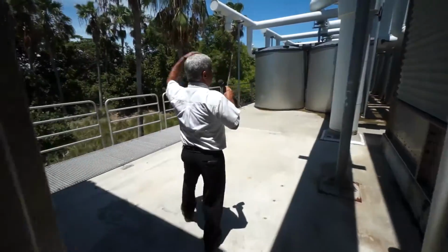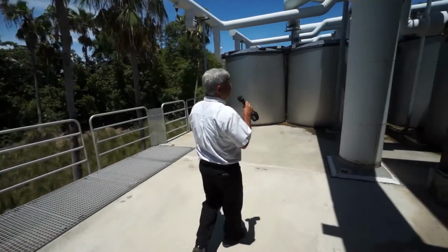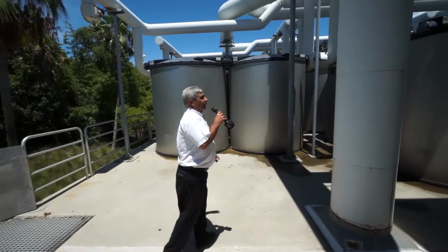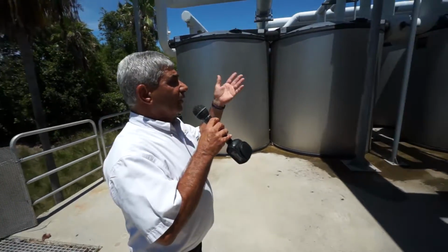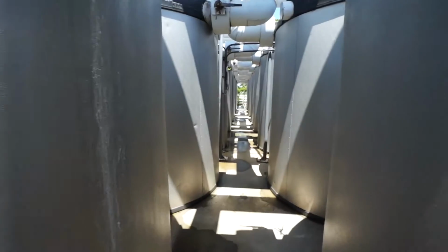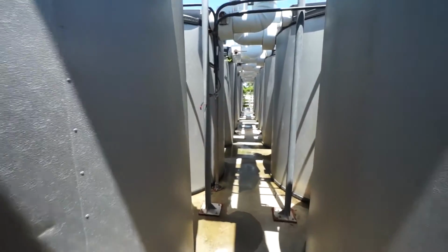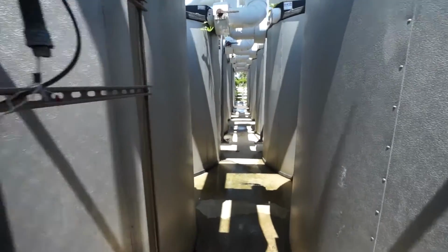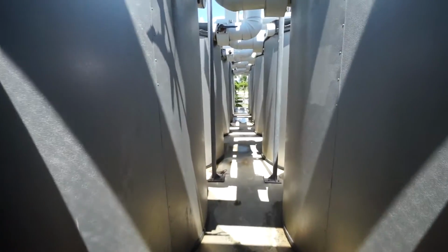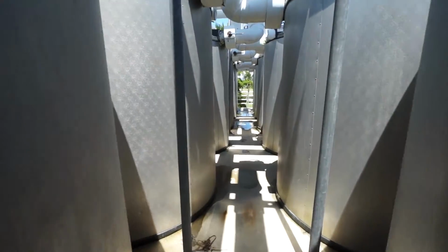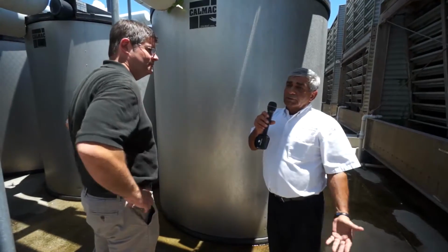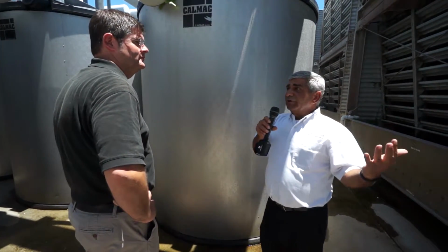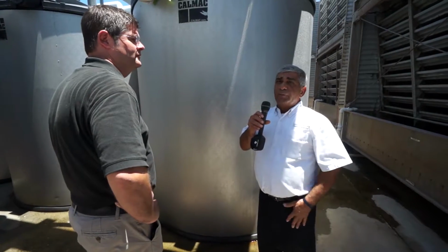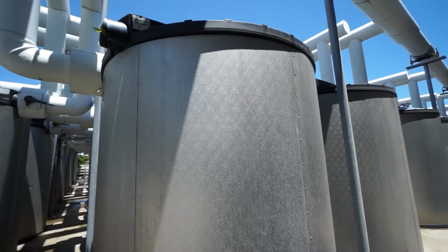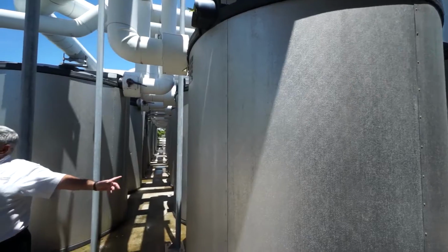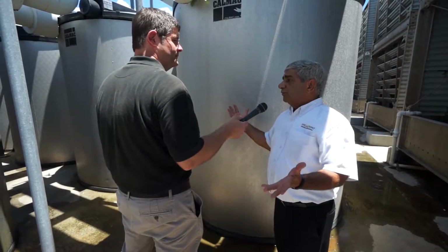Okay, now we're coming up on our ice tanks, which we call our ice farm. There are 240 of these tanks, 120 upstairs and 120 downstairs. It's just a solid chunk of ice in there with a coil running down with glycol through it, and through thermal expansion, I'm going to say that's the easiest term, it will melt the ice. Glycol pumps and the heat exchangers we're running inside are what melt it because it's a different temperature.